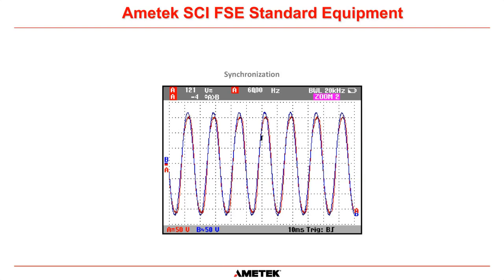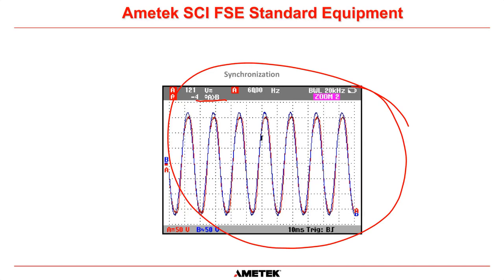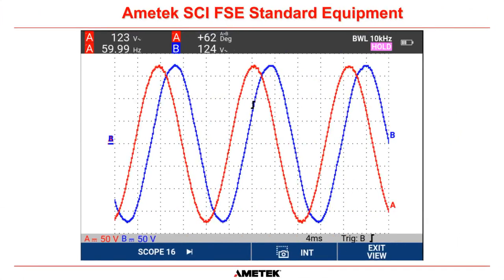Another waveform that we take is synchronization. So this is exactly what it should look like. The phase displacement between the two waveforms is about 4 electrical degrees. So it's difficult to tell here, but the red waveform is probably the inverter. The blue waveform is the bypass, and they should be perfectly synchronized together. Okay. And that allows a seamless transfer from inverter to bypass or from bypass to inverter if there is an issue. Now, if we walked up to a UPS and we saw this waveform, you can quite clearly see that red is the inverter, blue is the bypass. There is a phase displacement between those two circuits. And I think it says 62 electrical degrees. So this is not synchronized. And if you try to transfer from inverter to bypass at this point here, you'd cause a huge amount of circulating current, and you're going to trip breakers. You could damage the inverter. It would be a very bad day. So we have to make sure that the system is synchronized.